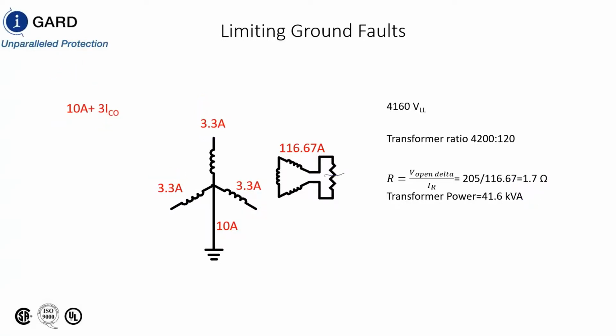And the other advantage is that you can put a pulsing contactor over here and change the value of the resistor and find where the fault is in medium voltage setups. And now you're switching at low voltage as opposed to medium voltage.